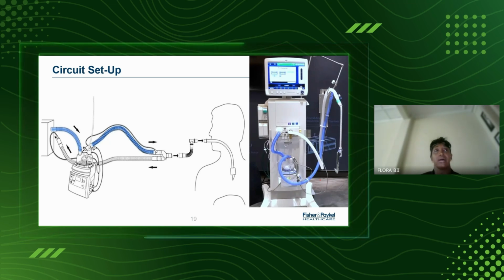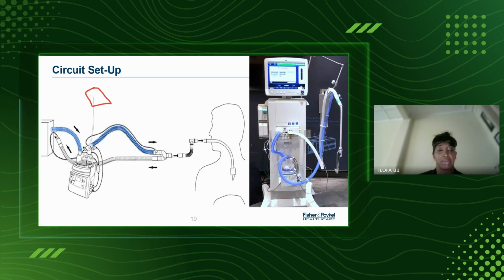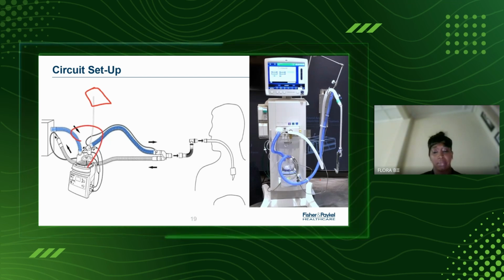The humidification chambers are quite different. Some have an auto-fill feature, meaning that it will draw water. Up here is where you would have your sterile water bag, which will be drawn in by a water feed set into the humidification chamber. Inside the humidification chamber there is what we call a dual float system, which will control the amount of sterile water drawn into the chamber. When it has reached the maximum fill line, the system will stop drawing any more water into the chamber.